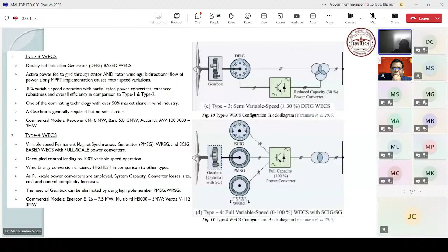I also have a few slides related to the converter controls. This is a PMSG based generation. So as I said, you have a turbine and you have a permanent magnet synchronous generator. So you have a full capacity bidirectional converter. Here you see you have one grid side converter, and you have the machine side converter MSC, where the PWM control under vector control operation you can operate it. This grid side converter has one major role, to maintain this DC link voltage.